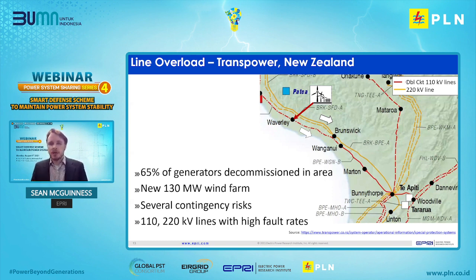So they installed, if you wish to move to the next slide, to mitigate these contingency overloads, an overload protection scheme to detect overloading on these lines and run back the wind farm to preset levels to reduce the overload. So if you'd like to move to the next slide.